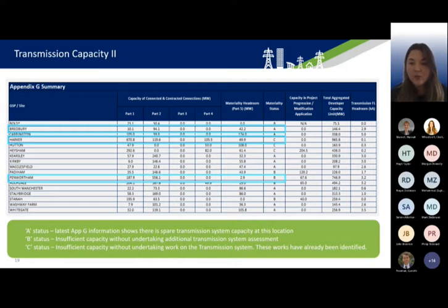Okay, so do project progression and MODAP have separate fees? So you'll pay a fee to go into project progression, so it's usually around £20,000. And then once you get to the MODAP stage, there are usually securities associated with that work. I can't really advise on what the securities will be because they depend on a project by project basis. They'll depend on the work that Grid are undertaking. They'll also depend on the size of the connection that you're looking to connect. And also they can depend on how far out you are from energisation. So Grid calculate those on a bespoke basis for each project.